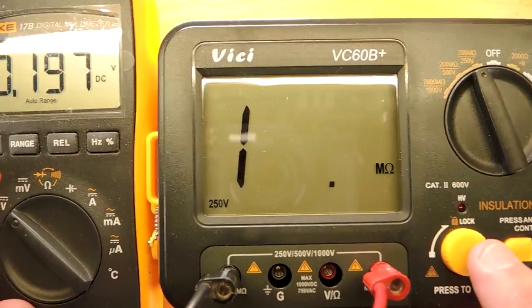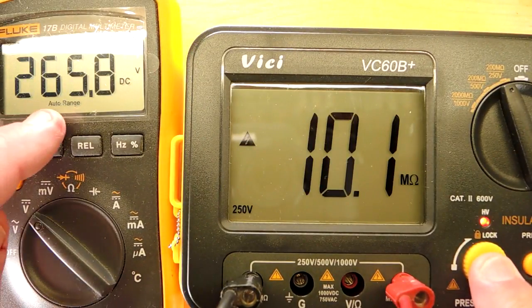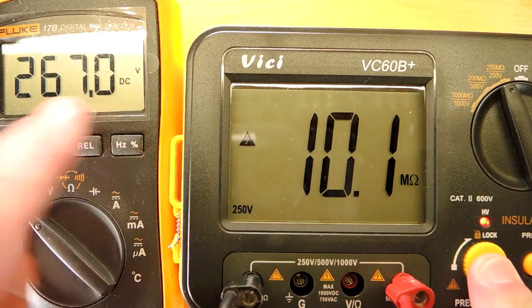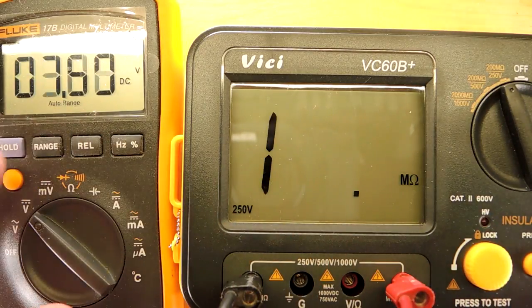In the 250 range, I can press the test button, and you can see it goes to about 250 volts, a little bit over, and declares that the resistance of the meter is 10 mega-ohms, which is actually quite correct. That's good for this meter, so the reading is quite plausible.